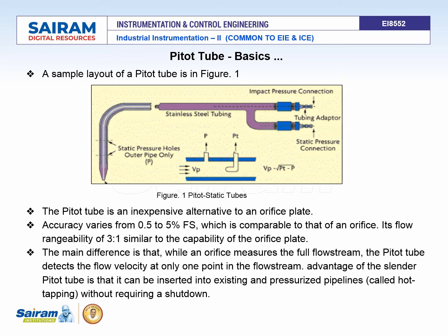And the advantage of the slender pitot tube is it can be easily inserted into an existing pressurized pipeline, also called hot tapping, without requiring a shutdown. That is a major advantage of the pitot tube.